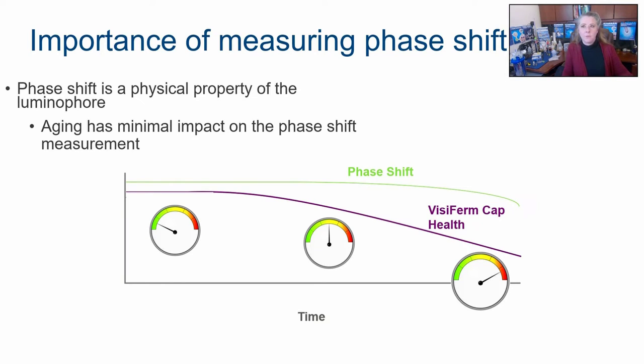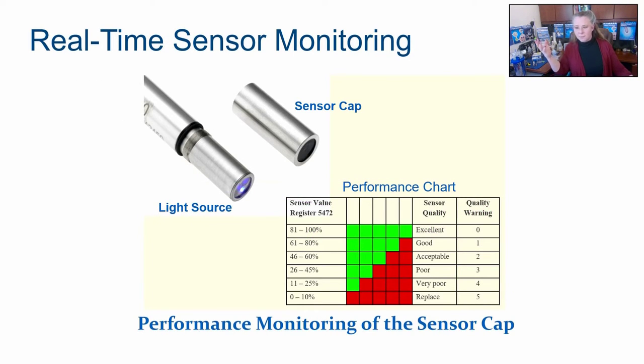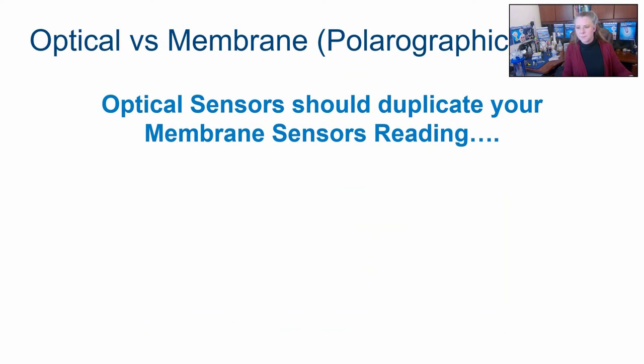So if you happen to have a process that's a seed train or a continuous process that's 60, 80, 90 days long, you can have confidence that your probe is going to be in good health and reliable through the entire 60, 90 day process. And that's a little harder to do in a polarographic probe. And it's not always easy to do in other sensors as well. Hamilton also just happens to have a software that gives you a report card on the health of your sensor. It monitors both the light source and the sensor cap quality and gives you a quality warning, and it tells you when you need to replace your cap. Just happens to be a convenience.